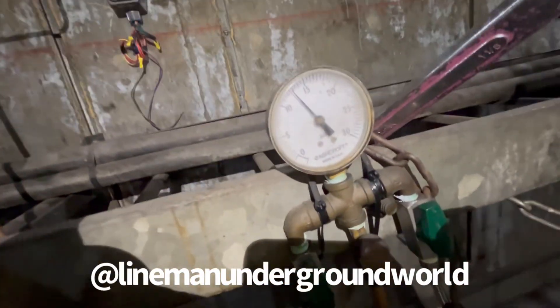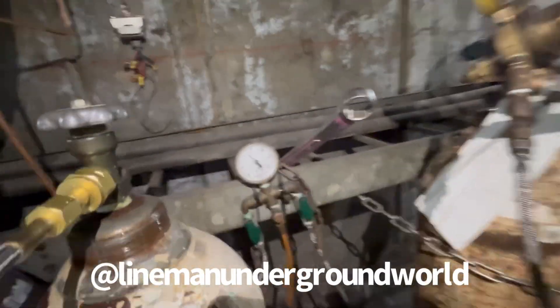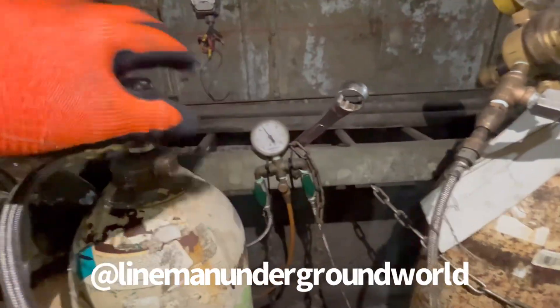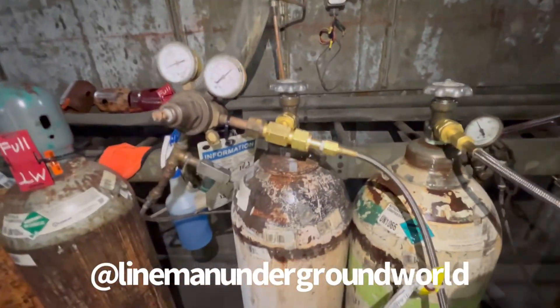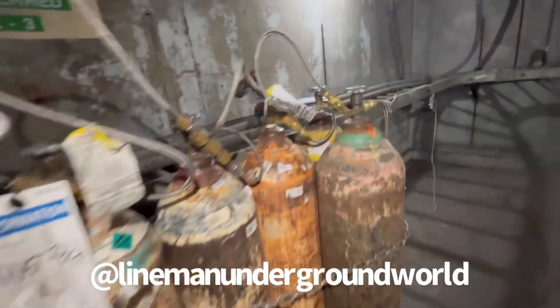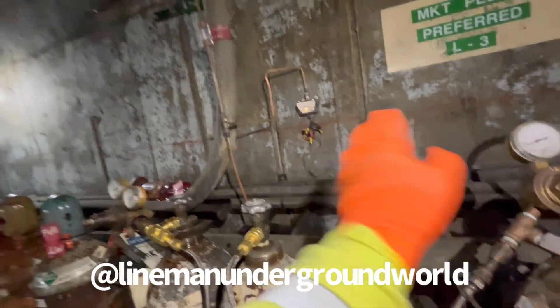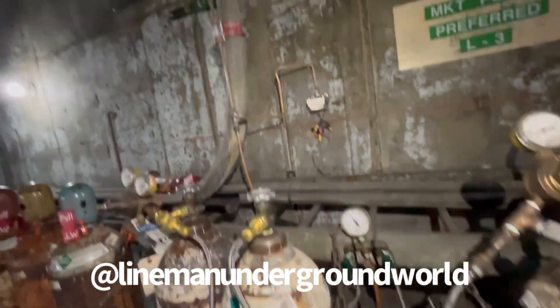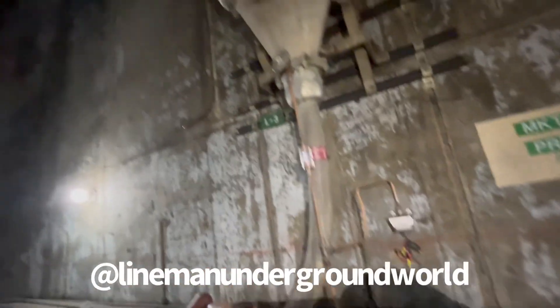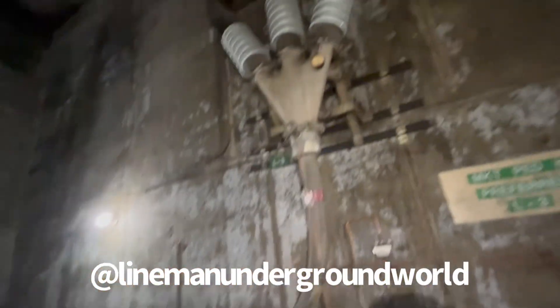Here we go — 12 PSI, that's what we want; it'll readjust once it stabilizes. And that's a wrap. We've got our alarm right there set for the highs and lows, so if anything happens and it goes flat it'll give us an alarm. Otherwise it's feeding these two cables here and keeping pressure to keep the water out.